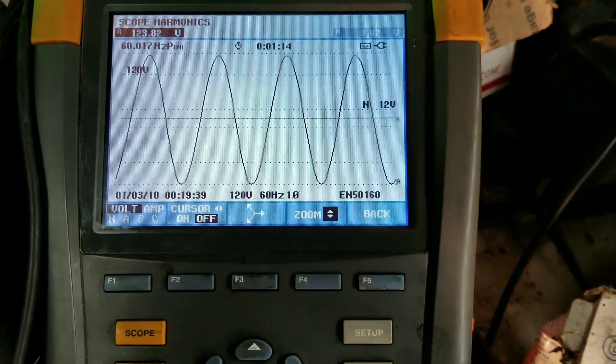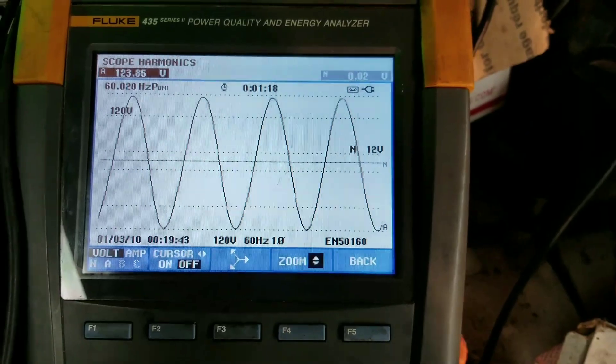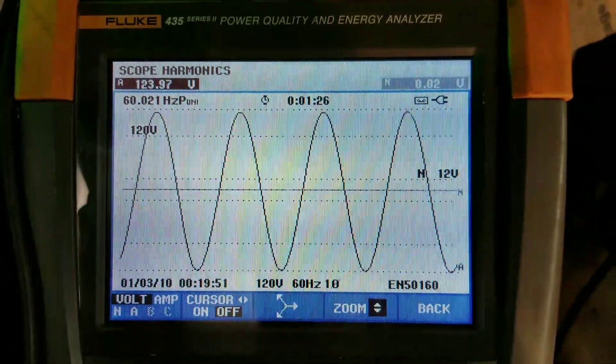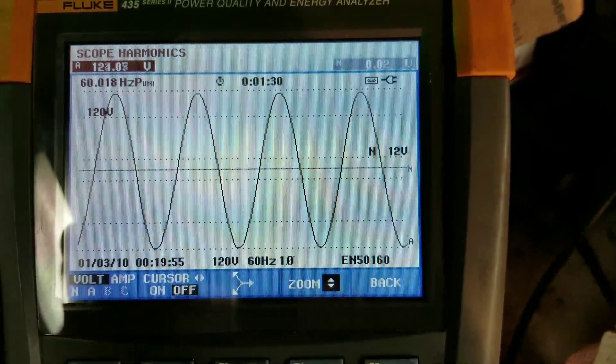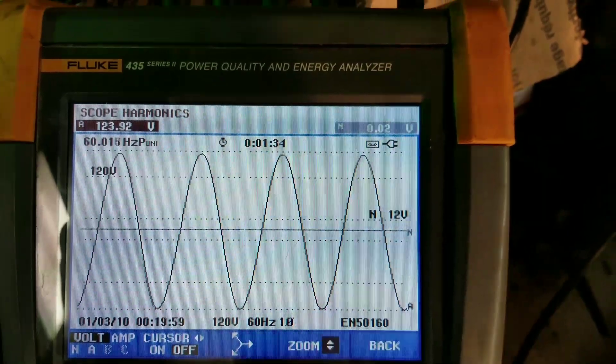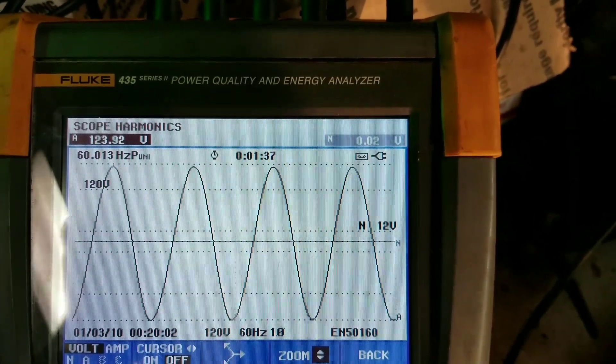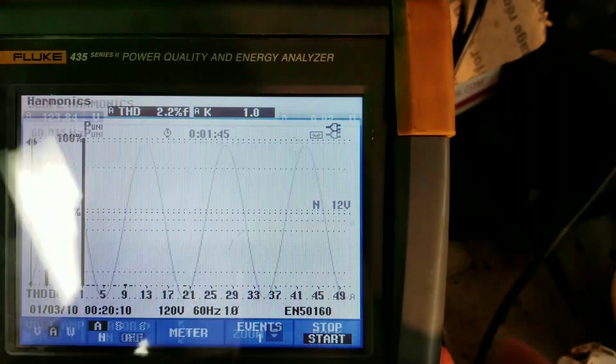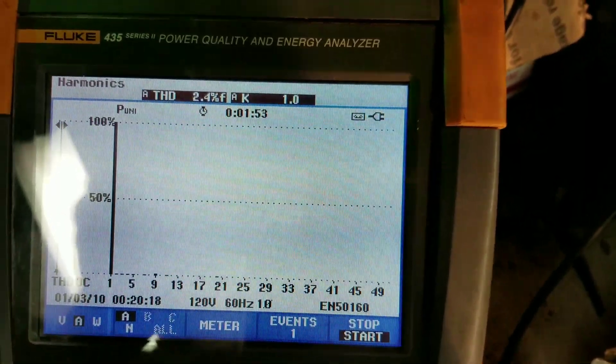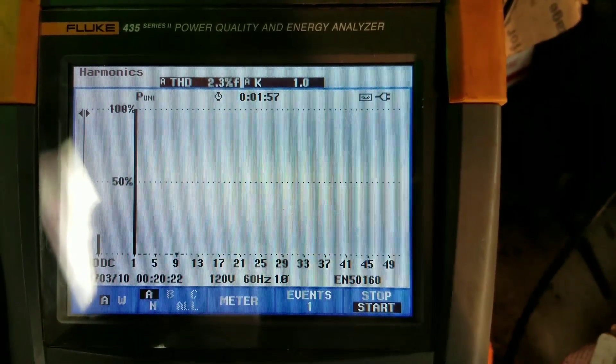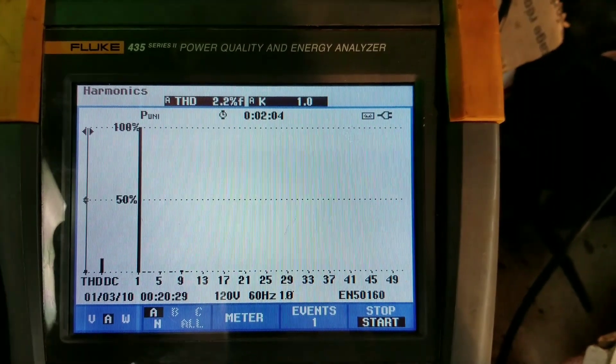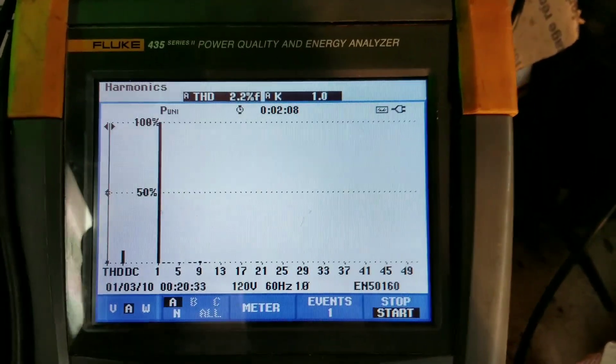Alright, so we're in the shop. Here is the sine wave, the AC sine wave coming off of the Predator. We're on eco mode right now. That's pretty damn good, I must say. Let's go back to, so here's the total harmonics of it right now, 2.3 percent. 2.2 percent total harmonic distortion. I've seen worse.